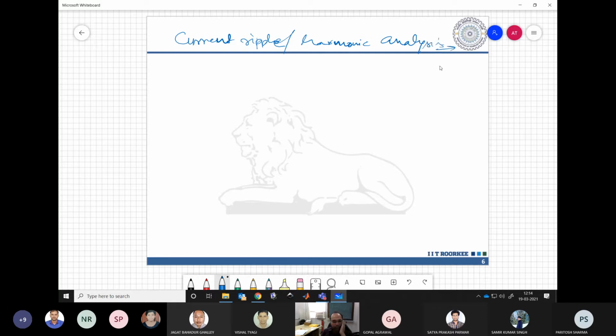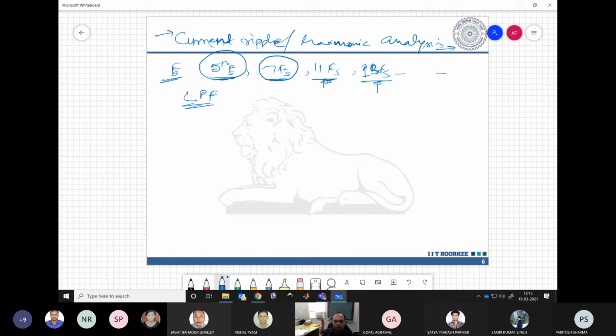Of course, for any PWM, if you want to quickly compare the performance, you must have some performance metric. That's what we have seen for the low switching frequency case. There we have the fundamental and then the fifth, so 5Fs, 7Fs, 11Fs, these are the components which are available in the line-to-line voltage or line-to-neutral voltage. Now, in case of low pulse number application, each of these components is very, very dominant. So we need to know what is happening at this particular harmonic level.